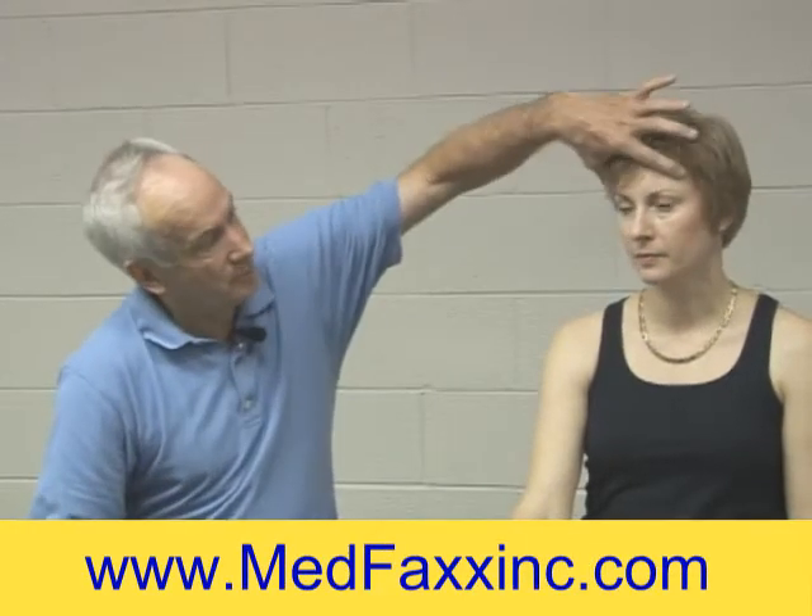One of the things I'll tell you right up front: you never put electrodes up on the head itself. There are a couple of reasons for that. The biggest reason is you have skin and then you have bone. Electricity likes moisture. You have fat tissue, as my wife Elizabeth, the physical therapist, has pointed out. But also, up there it can become uncomfortable. Please understand, I am saying that from a historical basis of using a TENS unit. When you use interferential, you're using 8,000 cycles per second, not 150.